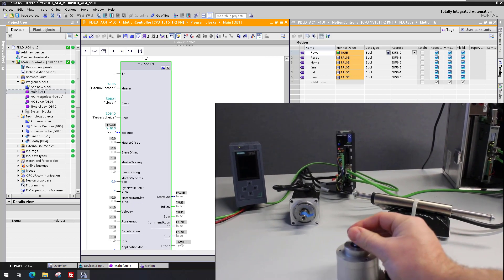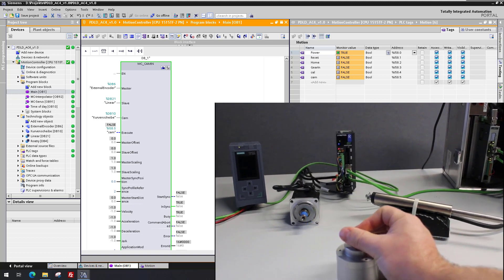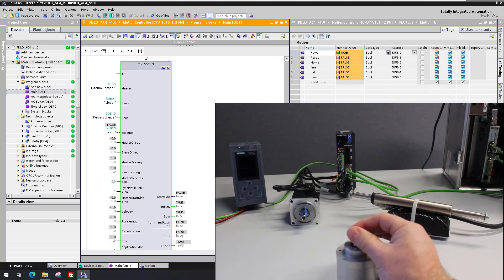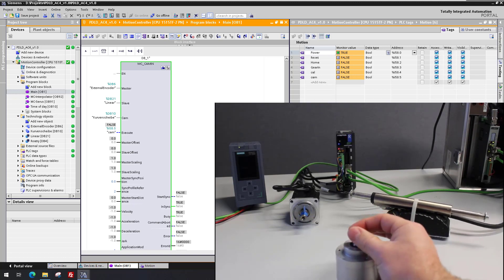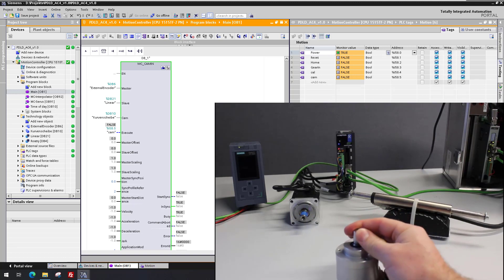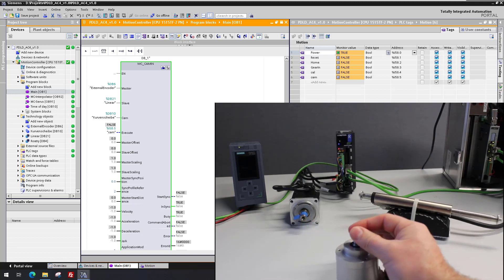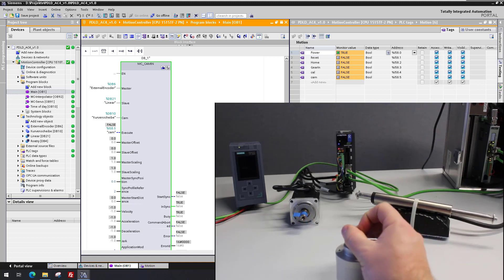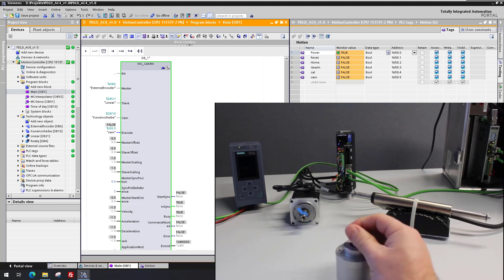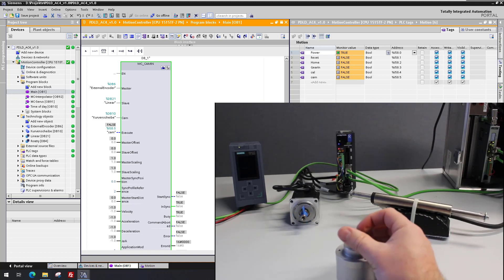Now the leading value is changed by moving the shaft of the external encoder, and the rotary axis follows with a linear gearing ratio — one revolution results in one revolution of the rotary axis. The linear axis follows the cam: one revolution of the external encoder drives the corresponding cam profile.